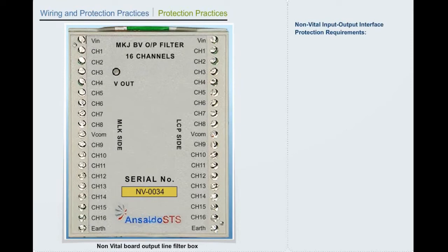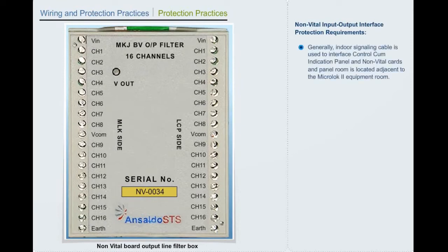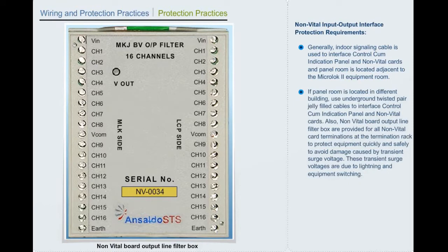Non-vital input-output interface protection requirements. Generally, indoor signaling cable is used to interface control-cum-indication panel and non-vital cards, and panel room is located adjacent to the Microlok II equipment room. If panel room is located in a different building, use underground twisted pair jelly-filled cables to interface control-cum-indication panel and non-vital cards.